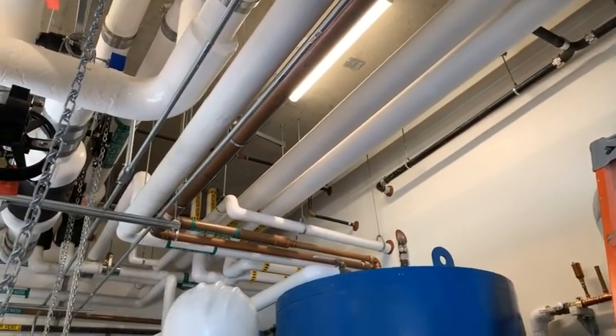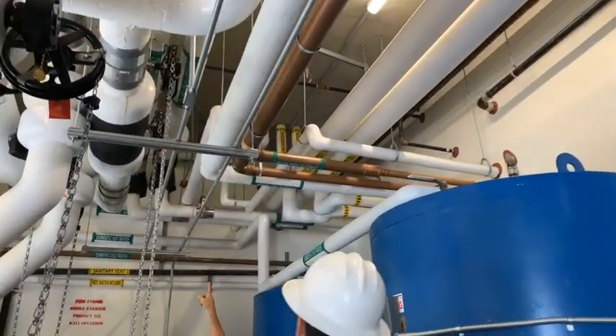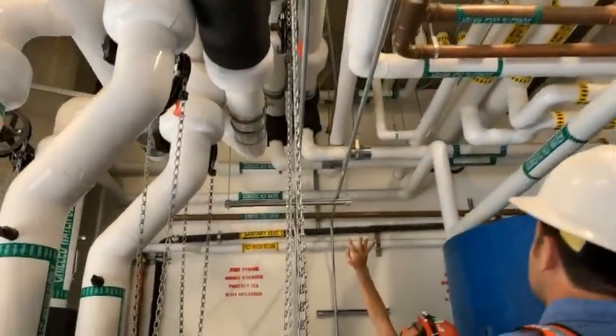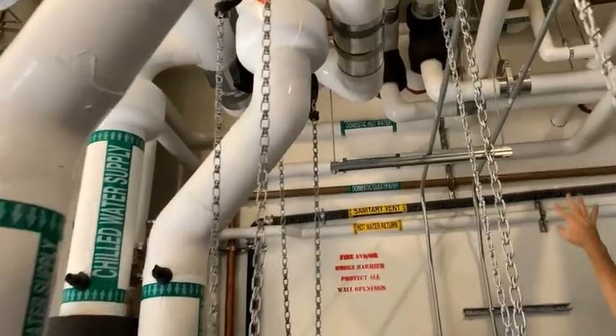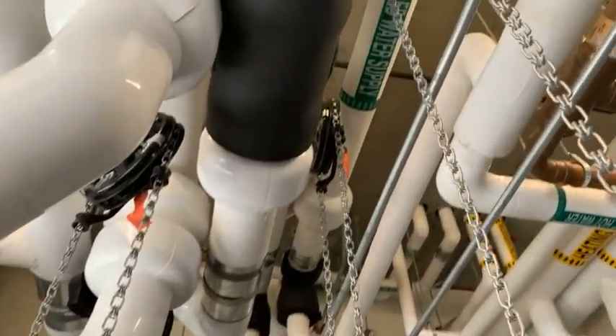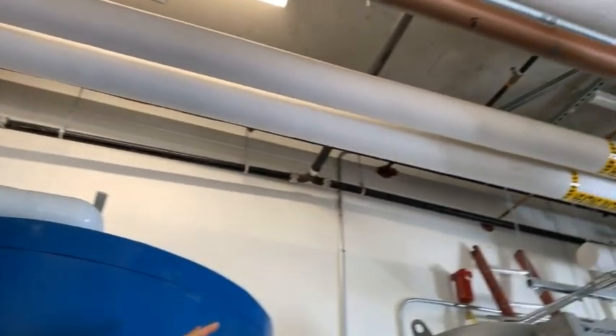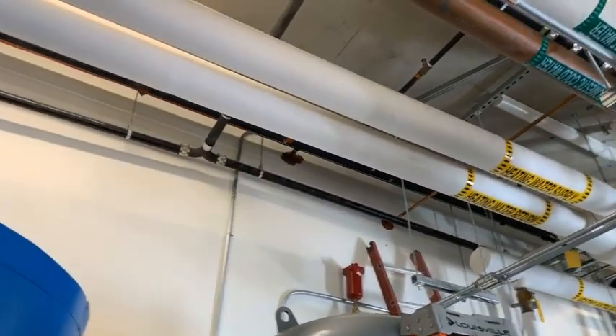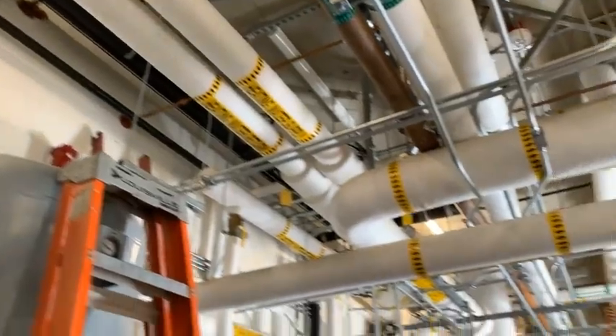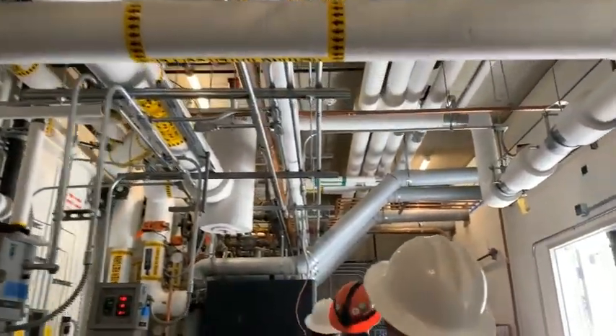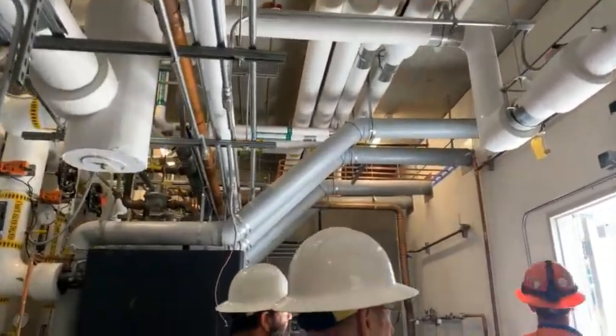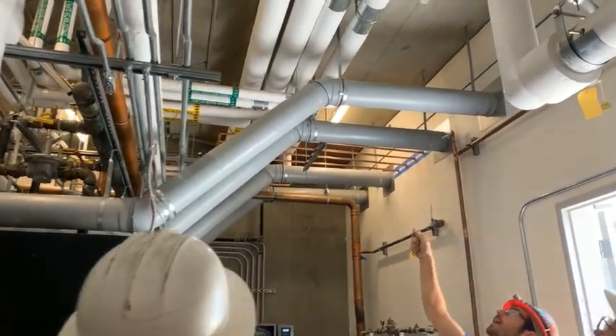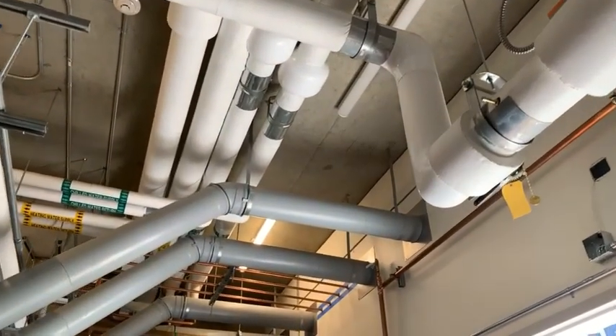Sorry, let's go, okay, right here. See these bubbles right here in the insulation? Sure. So that's going to shut off that side of the building. And then the 4 other ones. So we got the heating, right? Heating here, chilled here. The other ones are easier because they're all in a row. Shut off valves right here, 2 for heating, 2 for chilled.